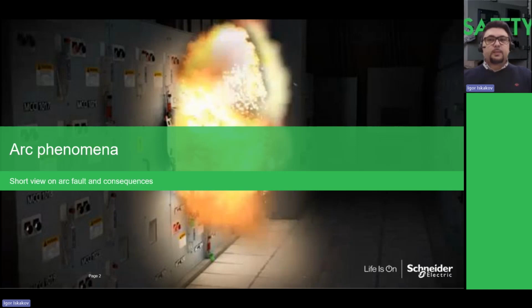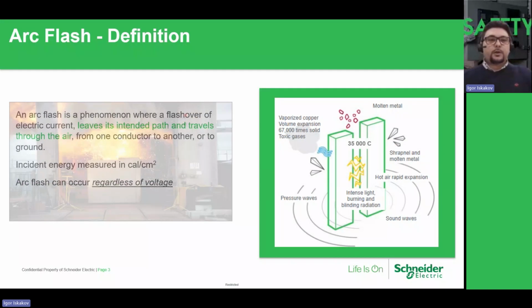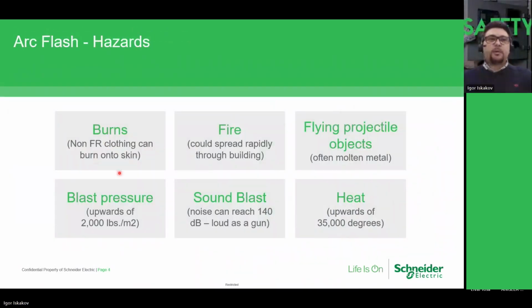First of all, I would like to speak about the arc flash phenomenon that, of course, everybody understood, but it's good to remember what is behind this. During the arc flash, there is a huge explosion between two conductive parts, and the temperature rises to more than 35,000 Celsius near the explosion. During this, we have pressure waves, sound waves, vaporized metal, and toxic gases. Also, there are shrapnel metallic parts and components of the switchgear which fly at the personnel who are near this switchgear. So these are factors which are very dangerous for maintenance personnel.